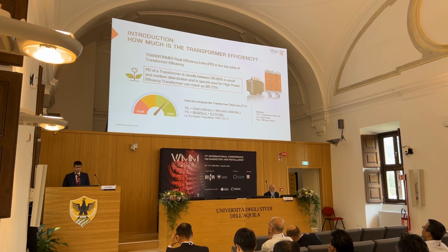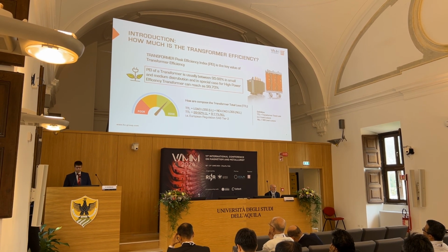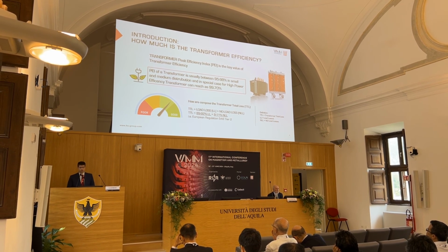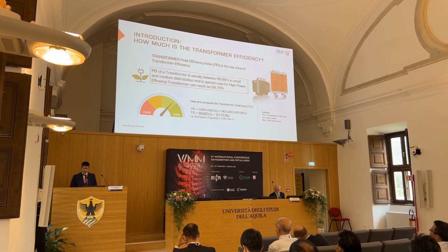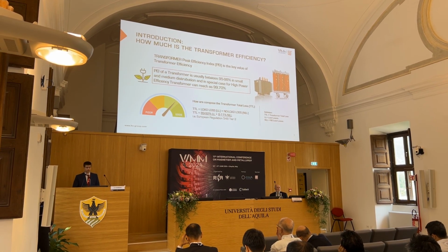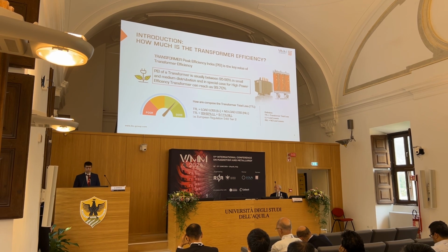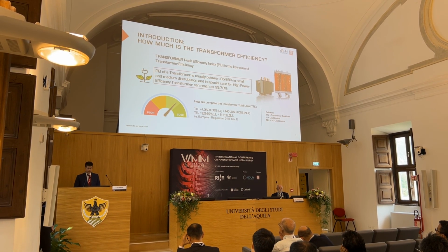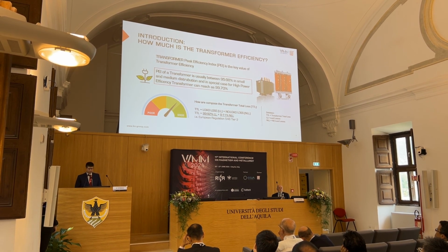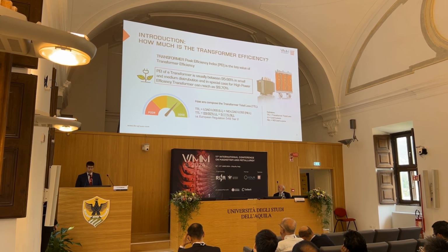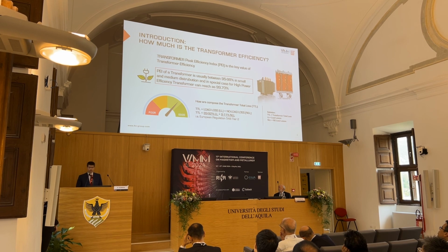All this information makes up the total efficiency of the transformer. In distribution and power transformers the efficiency is a little bit different, but we are already speaking of transformer equipment with an efficiency between 95 and 98% in the small distribution, and in the power and high power it can reach up to 99.7%.